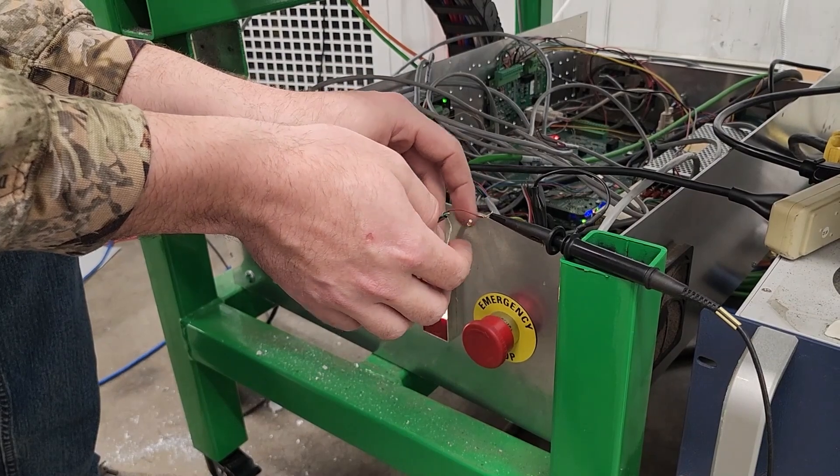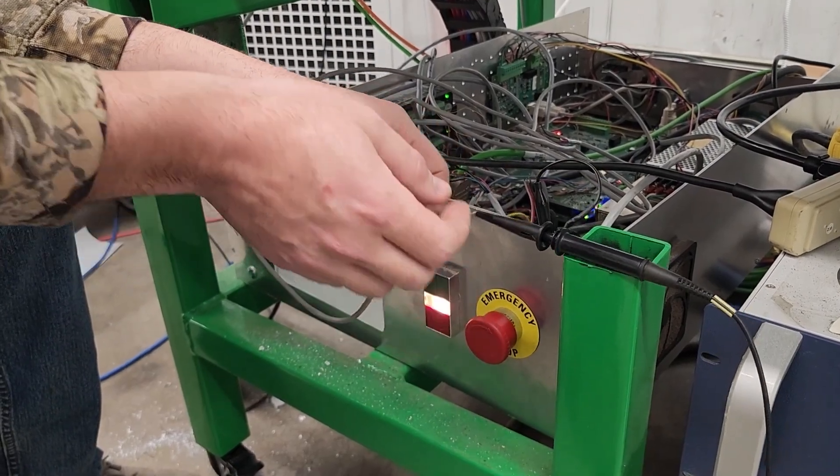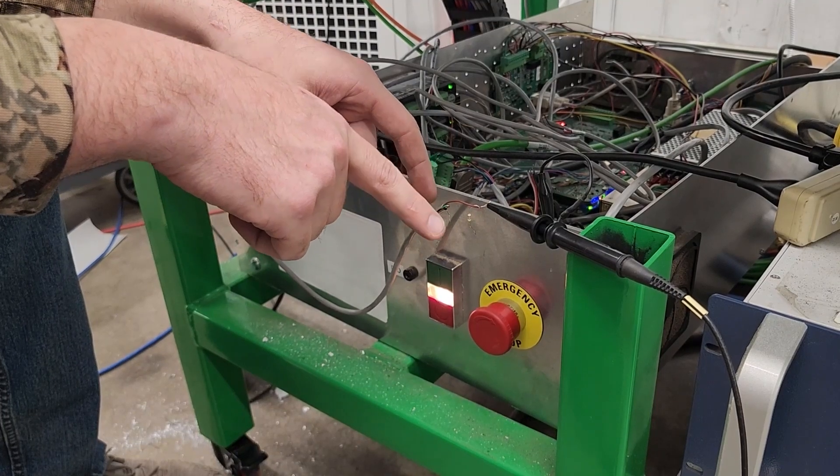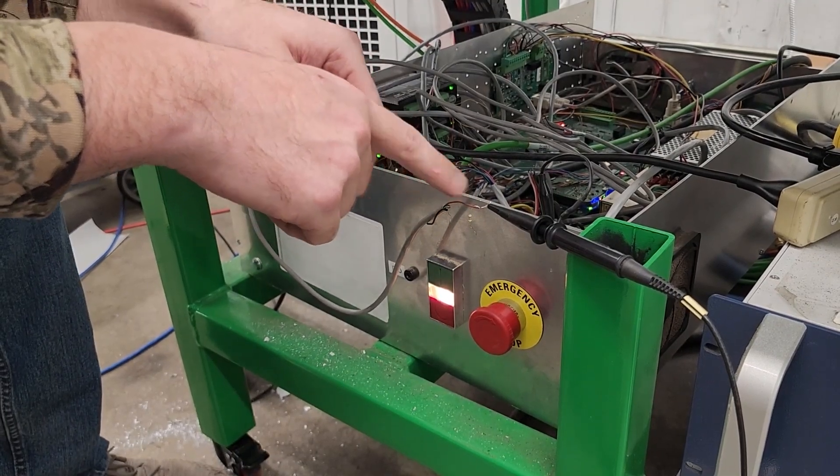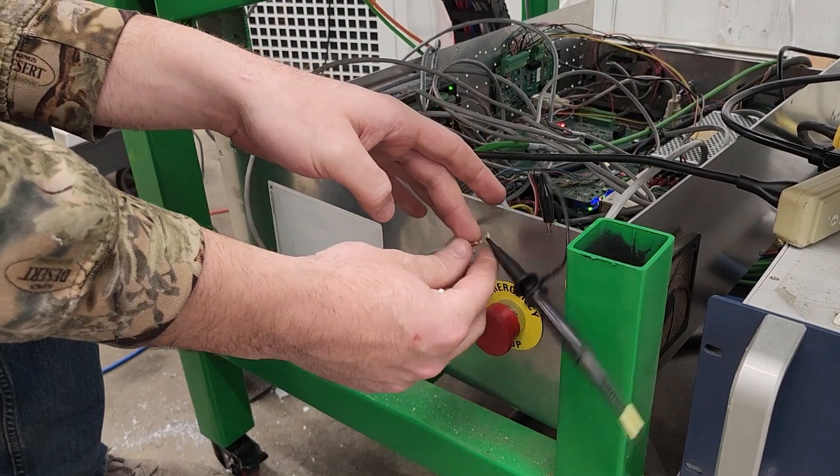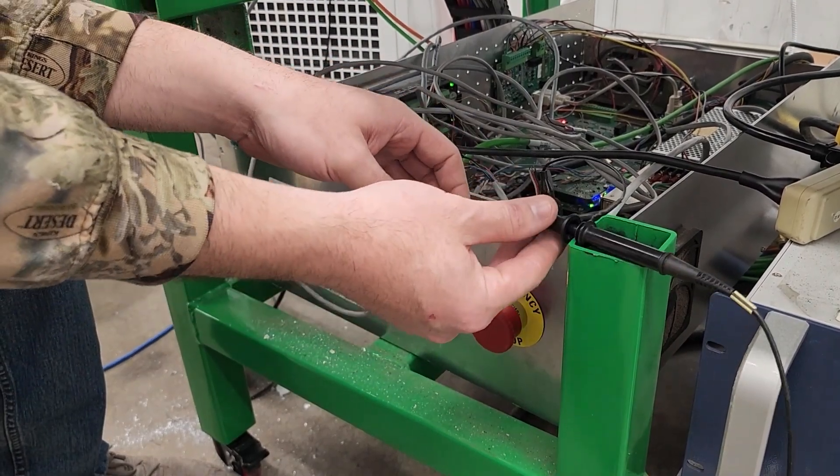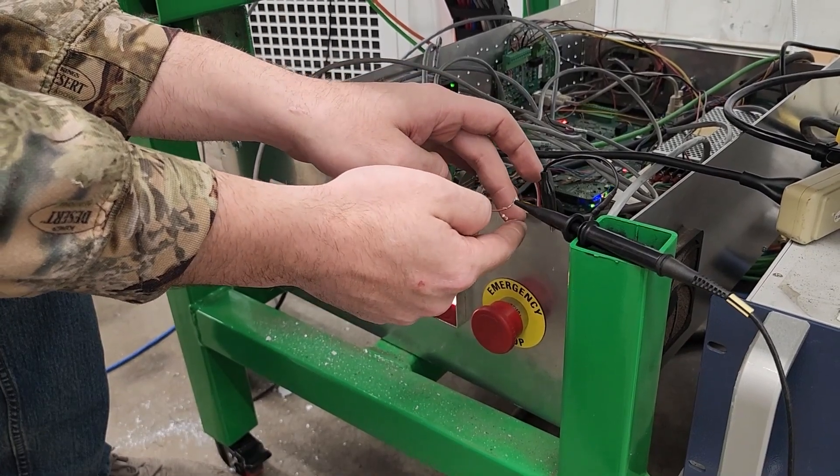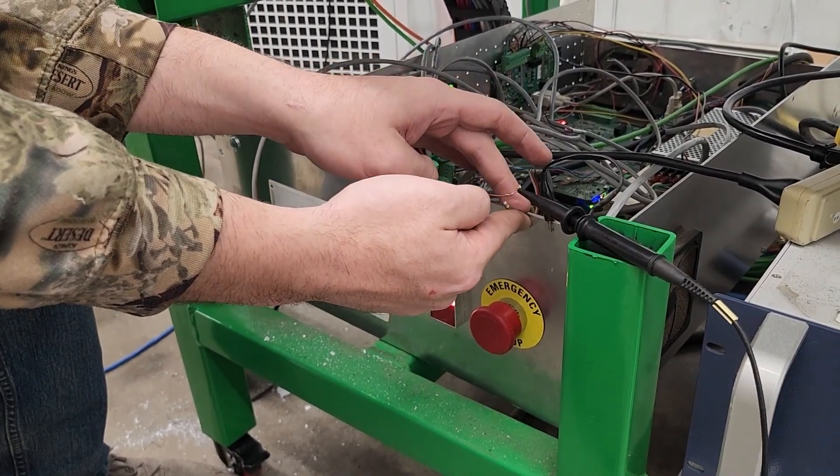While a resistor, we would want a resistor if, let's say, this wire is a signal wire and it's unshielded and there's noise in that wire being picked up, and we want to drain that noise. That's where you would get an appropriately sized resistor, and using it, you could then put it in parallel to drain off and filter off that noise.